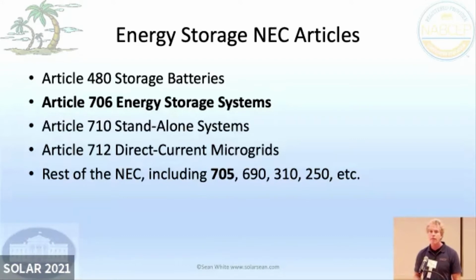And if you want to think of it, if you're talking Article 480, you're probably talking lead acid batteries or what are similar to NiCads, like these old batteries where you add fluids to them and they don't come with an inverter built into them, or they don't have an electronic off switch. They're not listed to all these new energy storage system terms. And then 706, that's the modern one.